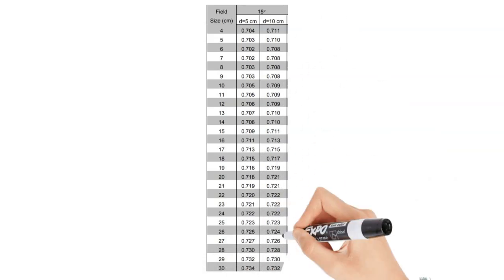Here's a nice example of a wedge factor table for a 15-degree wedge. These are all along the central axis. You can see field size increases as you move down, and wedge factors are listed at different depths. Generally, as you increase field size, the wedge factor goes up, and as depth increases, the wedge factor also goes up, at least until you get really deep.